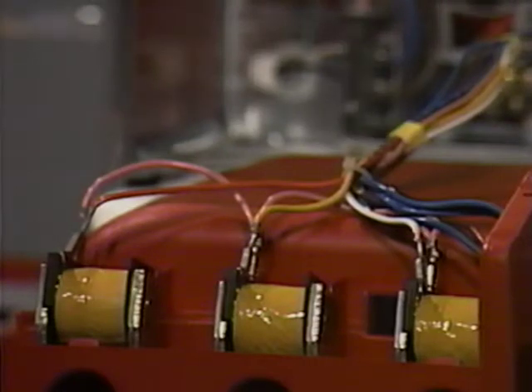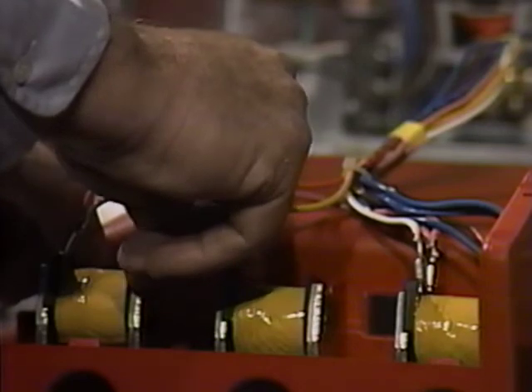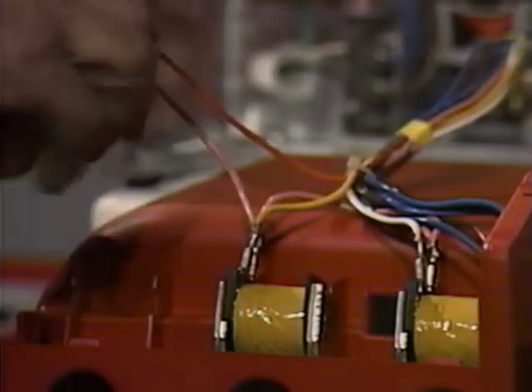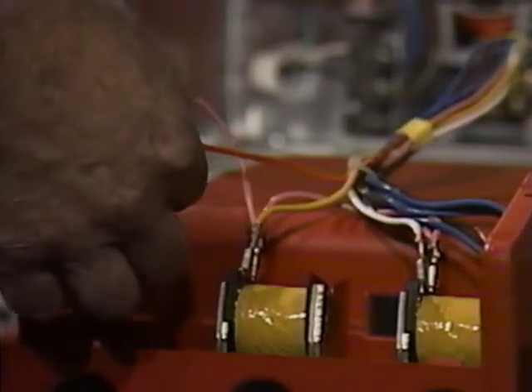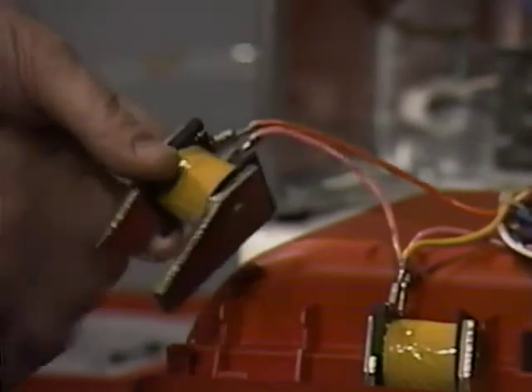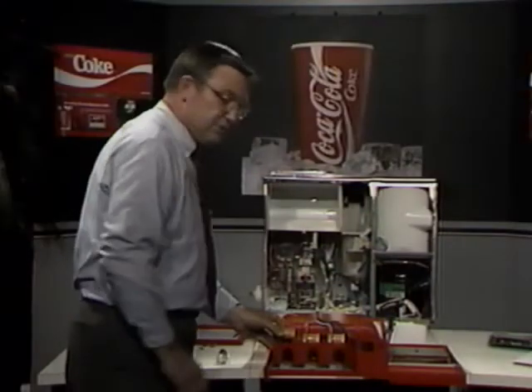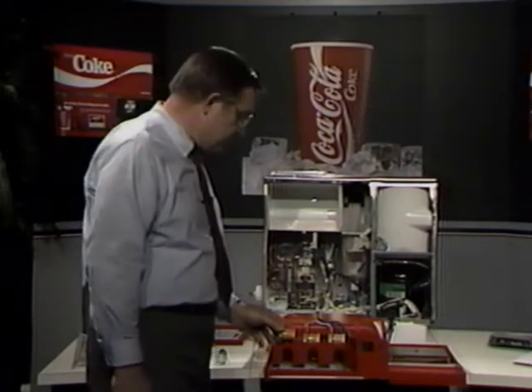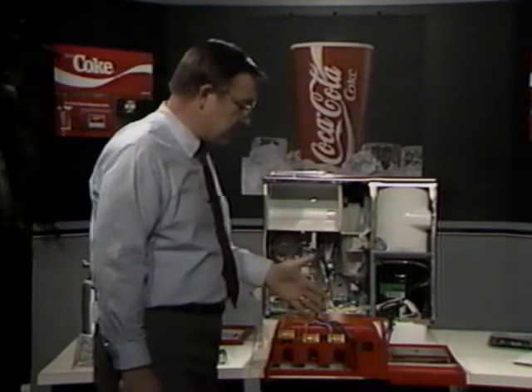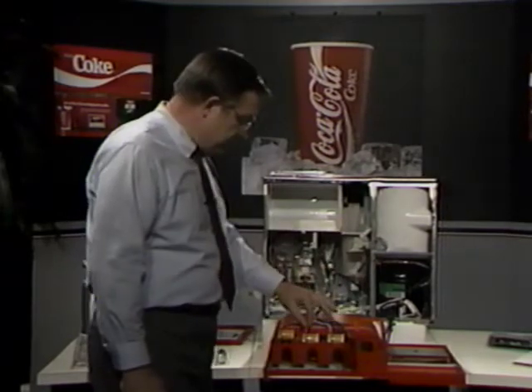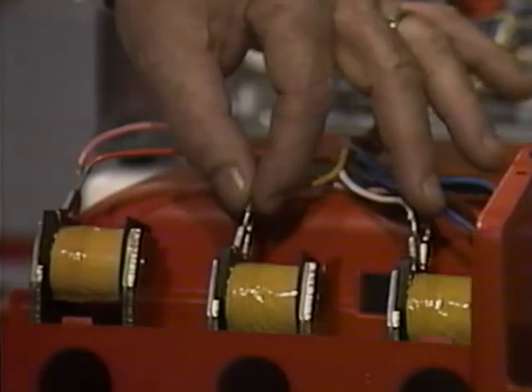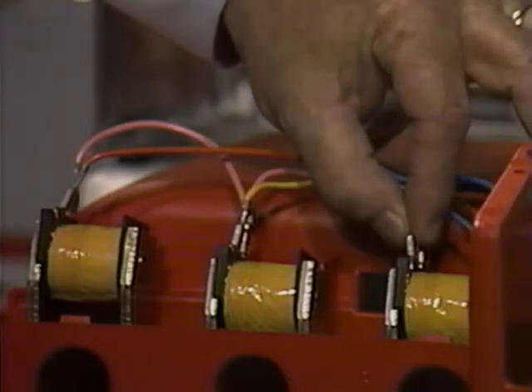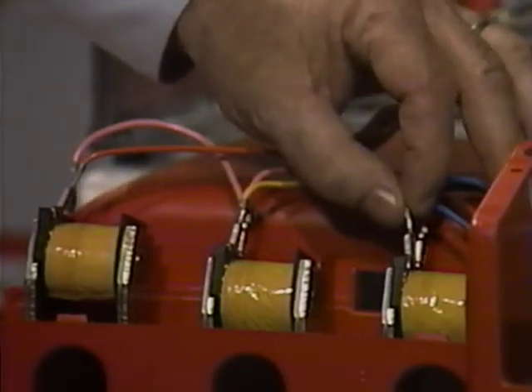With the front panel down, the thing you can see most readily is the doser coils. If you ever have to remove one, it's very easy. You just pull the tabs aside, lift the doser coil out, and disconnect it from the wires. Now, just a word of caution, it's good not to disconnect the wiring harness unless you absolutely have to and take the front completely off, because they're on so tight that you can risk damaging some of the little connections just by taking them on and taking them off.